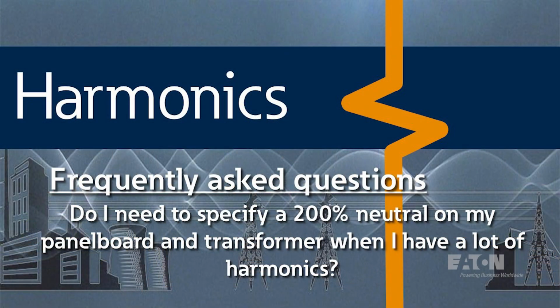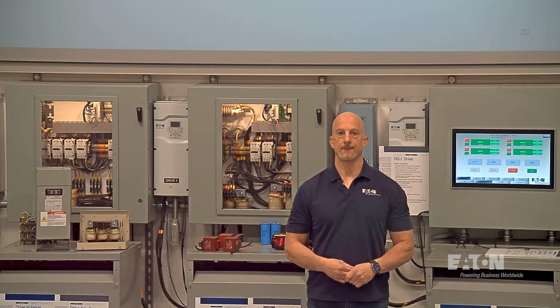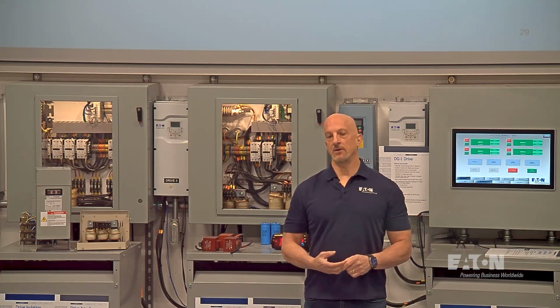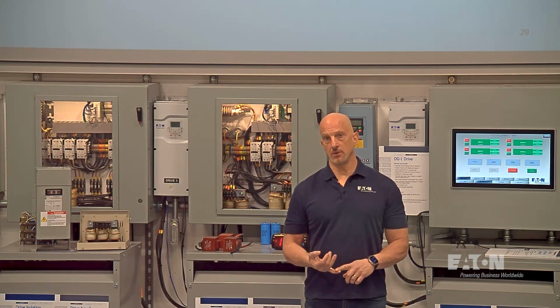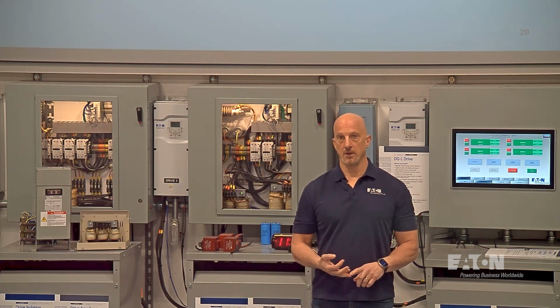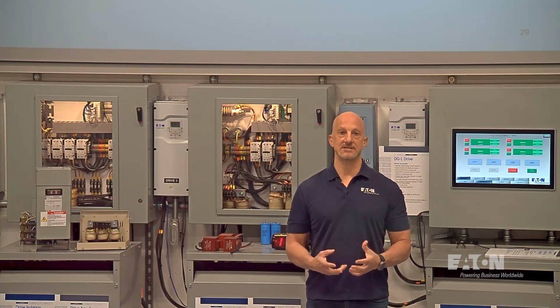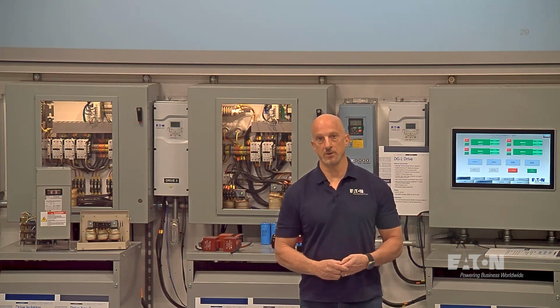So do I need to specify a 200% neutral on my panel board and transformer if I have a lot of harmonics? To answer the question about oversizing your neutral on your transformer or on your panel board, we have to think about which harmonics we see as to whether or not we care about oversizing that neutral or transformer. Let's take a look.